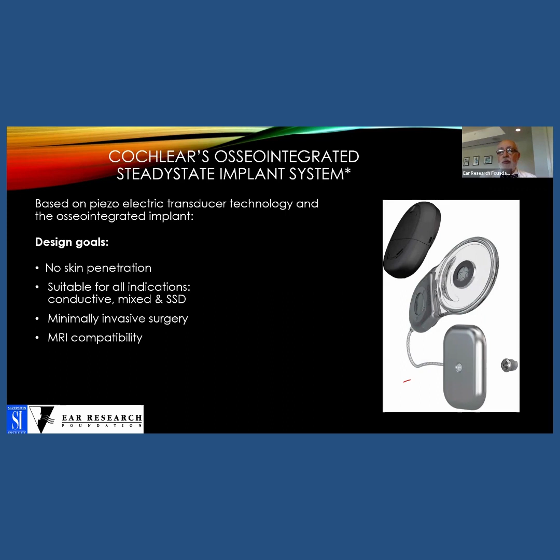The problem with this particular model, which is the magnet model, is that in today's technology, it is not MRI compatible. So if we feel that somebody needs MRIs of their head on a regular basis, we prefer to do the Connect, which is that small clip that you saw earlier. That is MRI safe because it does not have a magnet. It connects with like a stamp. The ones that need a magnet interferes with the MRI. So if we are doing it for a case, for instance, if you had an acoustic neuroma, which is a tumor of the hearing nerve on that side, we do not use the magnets because we want to monitor that neuroma with MRIs over time, and therefore we would prefer the Connect.